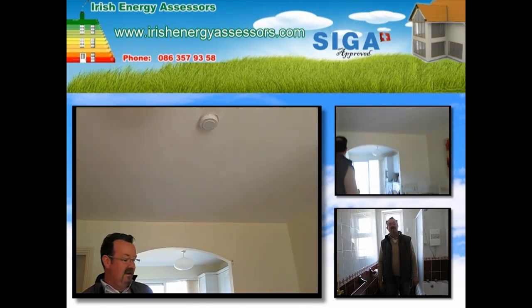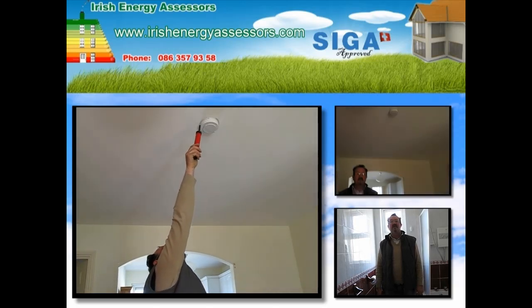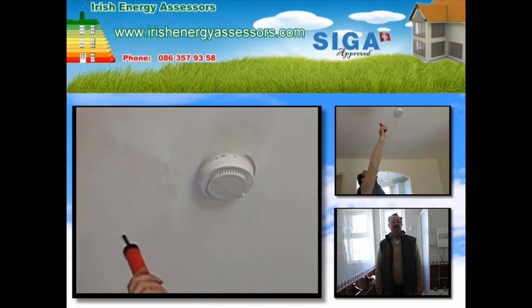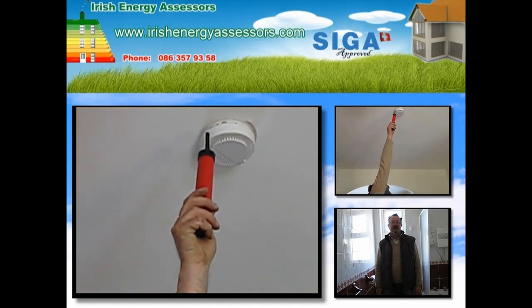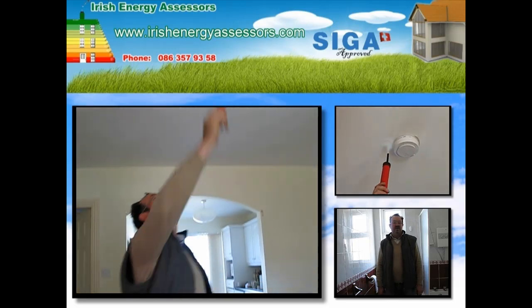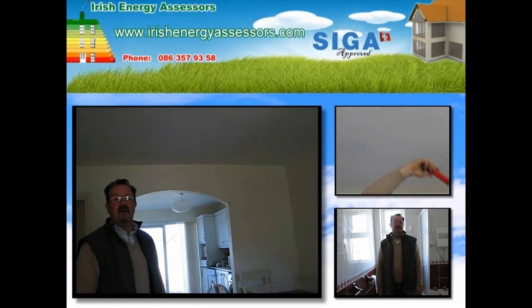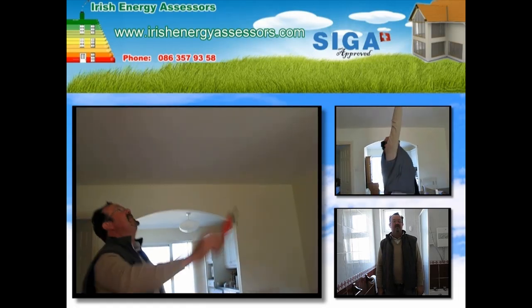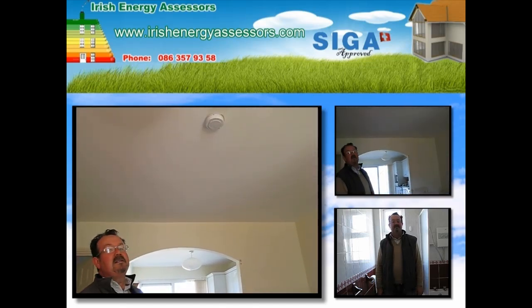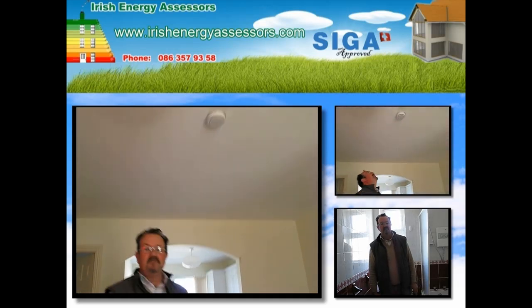This is another area that, unless it's properly sealed, will also result in heat leakage or air leakage. The smoke has been blown away from the detector, which means the air is circulating right around this house and coming down through that smoke detector. All these areas we can repair — they can be caulked up properly and sealed. The fan will identify all these areas in the house that are causing air leakage.